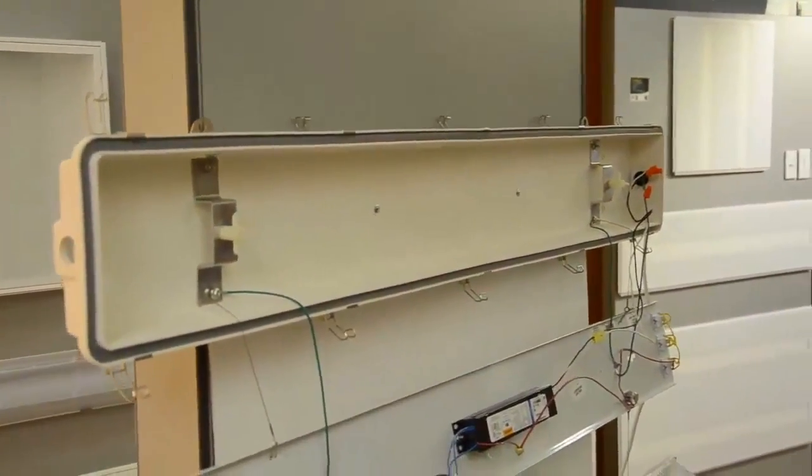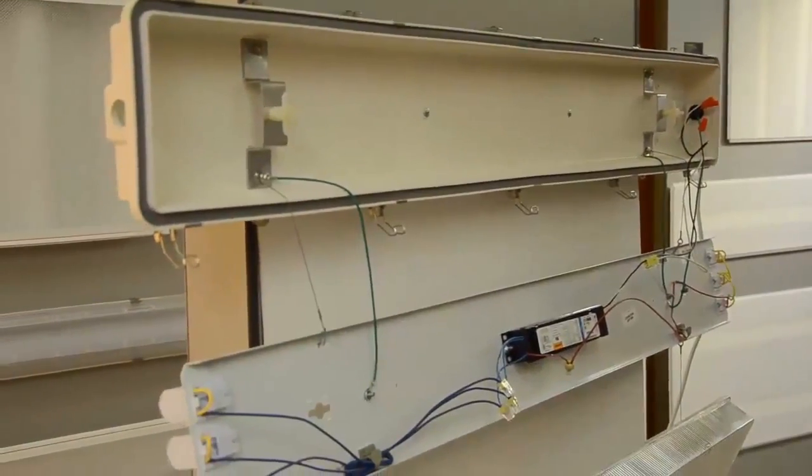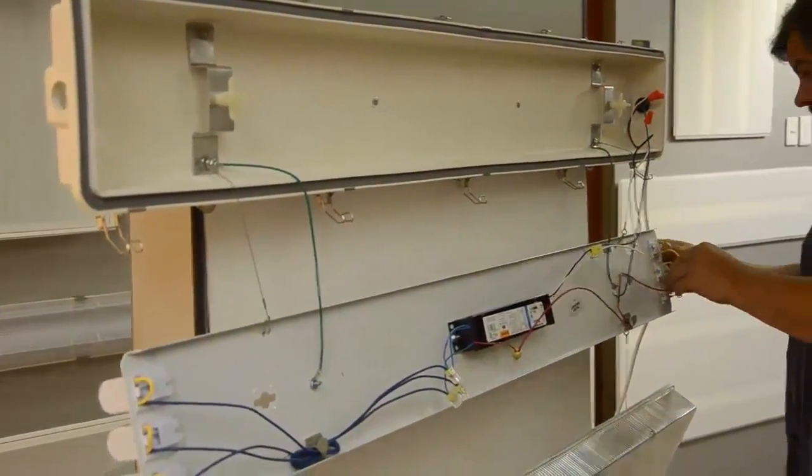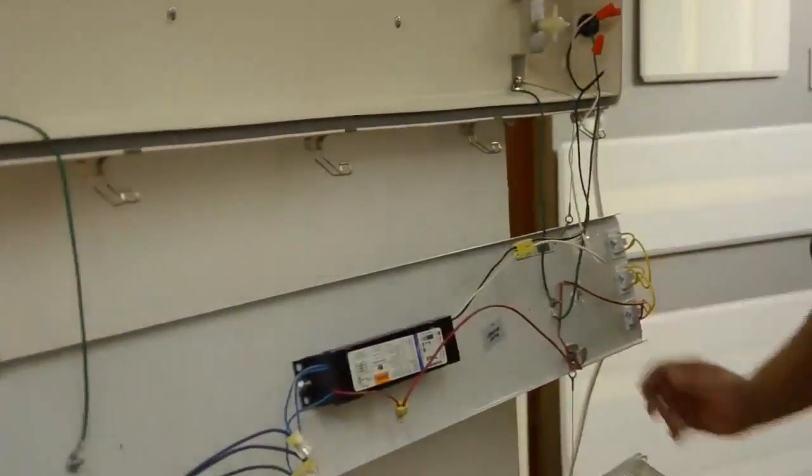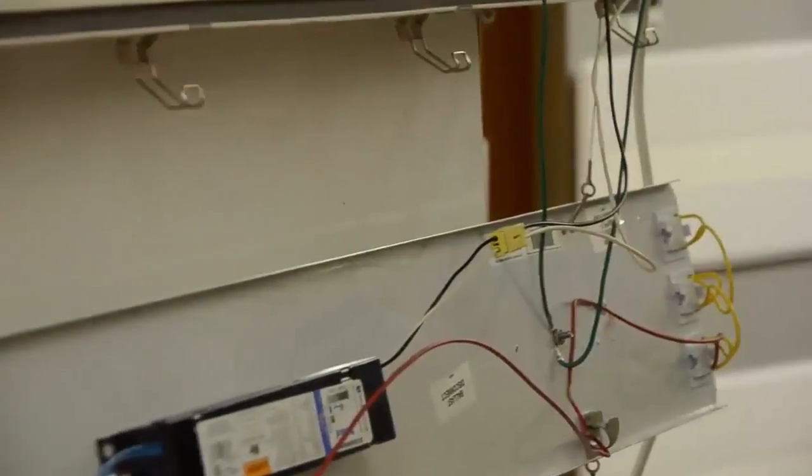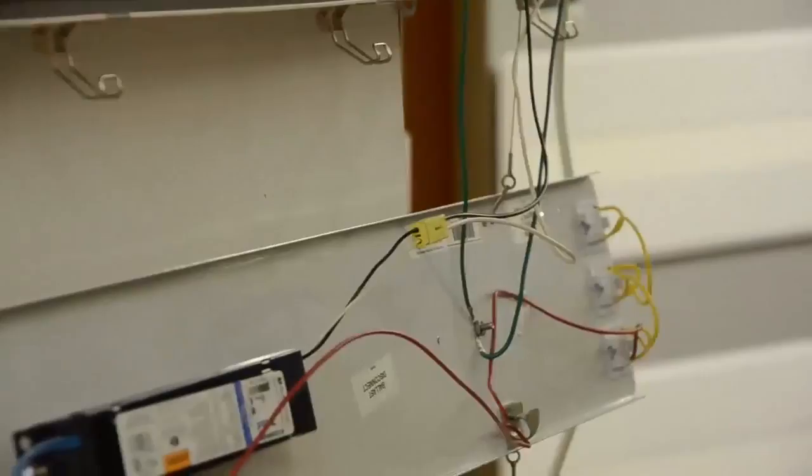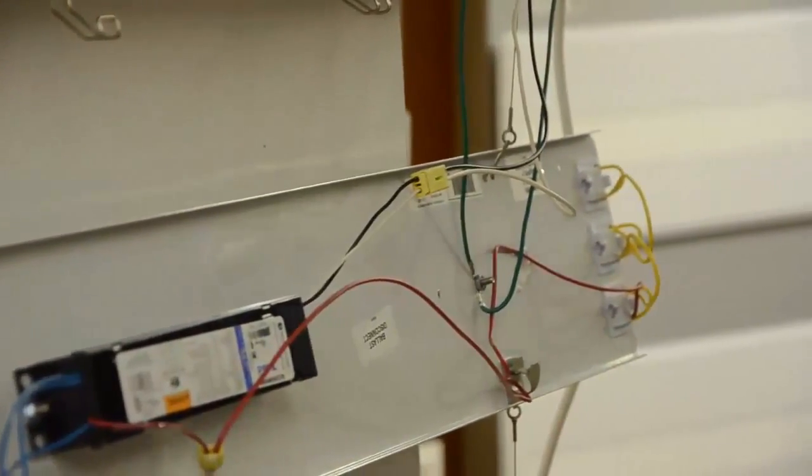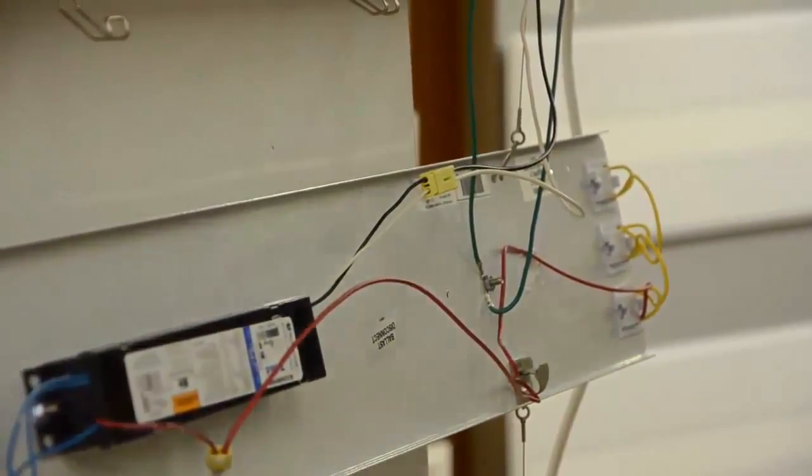This is a nice fixture to work with. First, we're going to identify our sockets. Clearly, these sockets are shunted sockets. The MaxLite internal driver LED T8 requires non-shunted sockets.